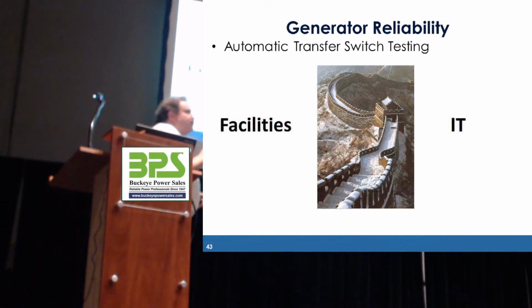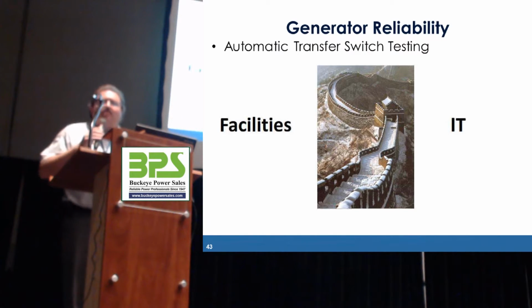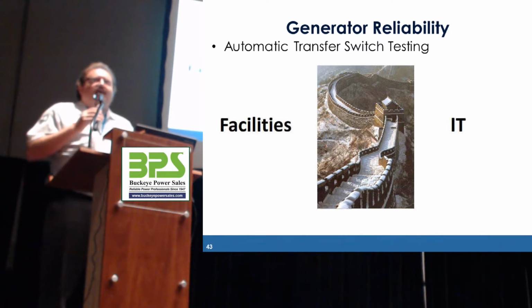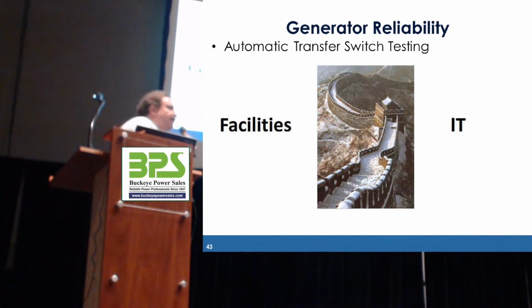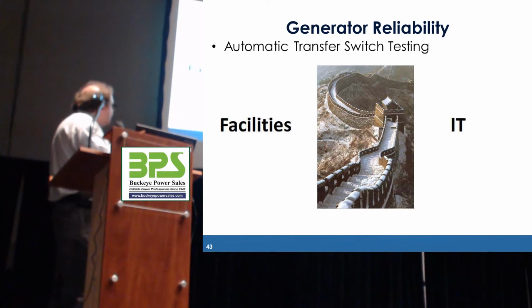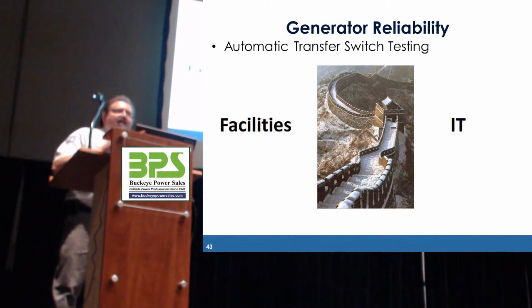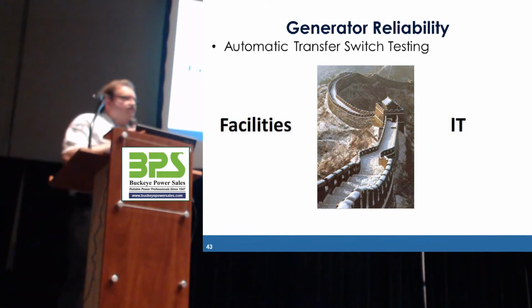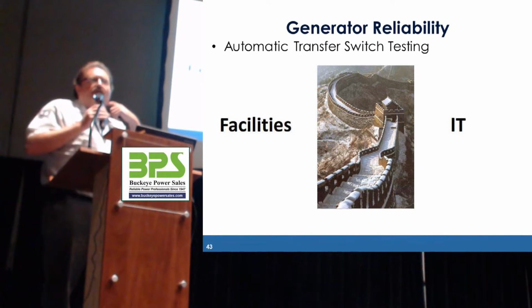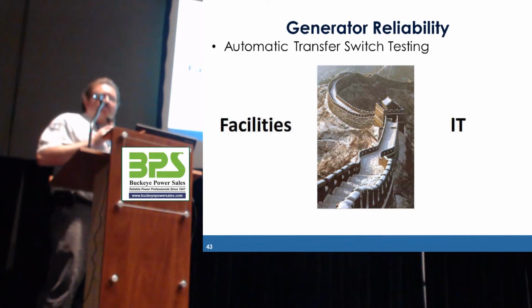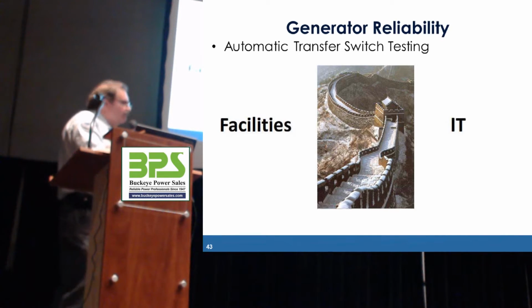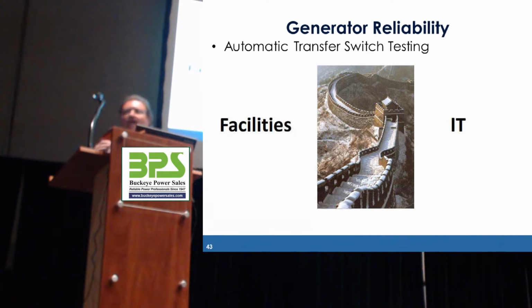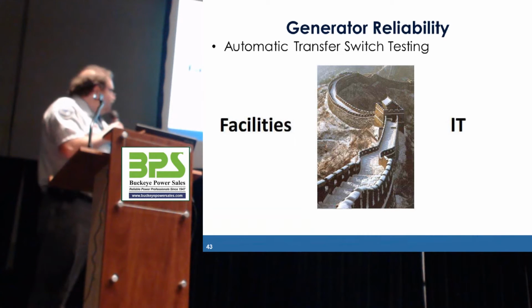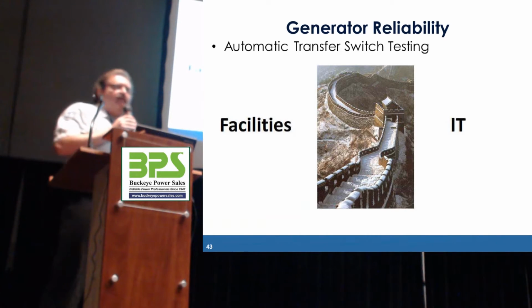The second major portion of your EPSS is the transfer switch. This is the area of the most contention when it comes to testing, because you have the facilities people over here that say we have to test this transfer switch. Code says we should do it monthly. We need to do it to make sure that it works. IT's over here saying, no, I cannot afford any type of an outage, and there's a giant wall between them.